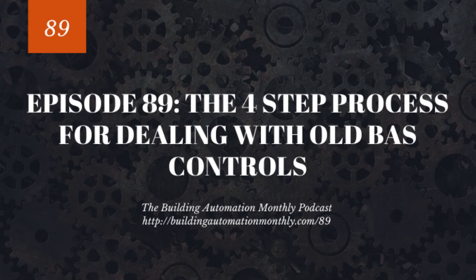Now, what do you need in order to implement demand control ventilation on an air handler usually? You usually need controls. So maybe you start with a combination supervisory/field controller device that can have a field trunk hanging off of it for a limited number of controllers.